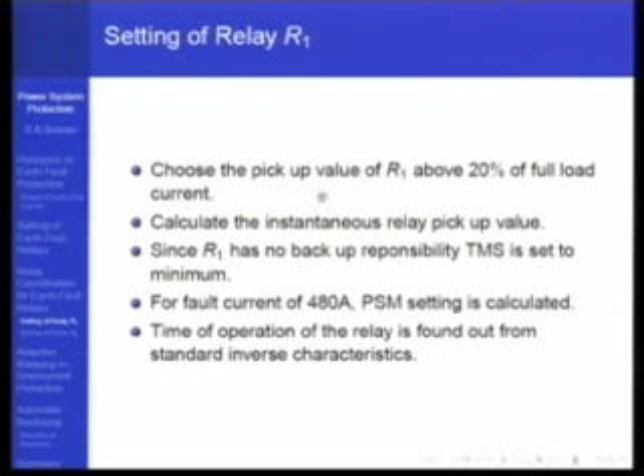Okay, so the fault currents are given here. The SLG fault current at bus A is 480 amperes and at bus B it is 650 amperes. Compute the time required for R2 to clear the SLG fault. The coordination time interval is given. Maximum system unbalance is 20%. So for the setting of R1, choose the pickup value of R1 at about 20% of the full load current, because unbalance is 20%.